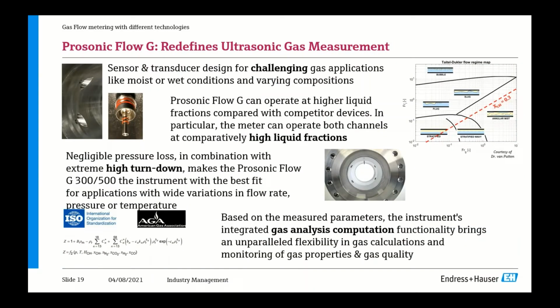So we really say that the Prosonic Flow G, our new ultrasonic gas flow meter, redefines ultrasonic gas measurement. And why is that? Because we designed this device really for challenging gas applications. Of course, it can measure dry gas, like natural gas, for example, but it can also handle very well more challenging conditions like moist or wet gas, or varying gas compositions. And there the device really excels.